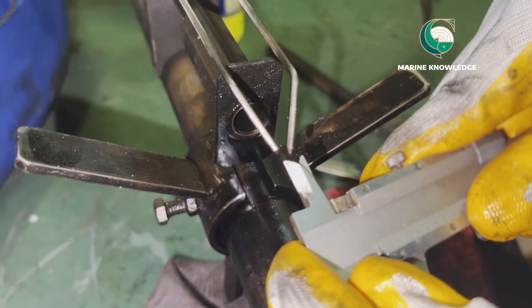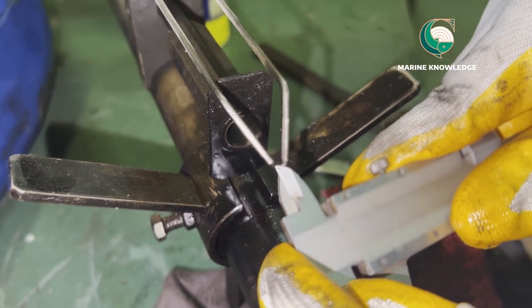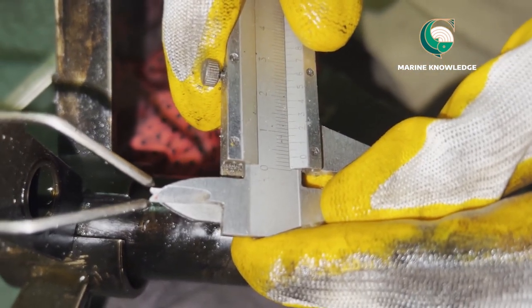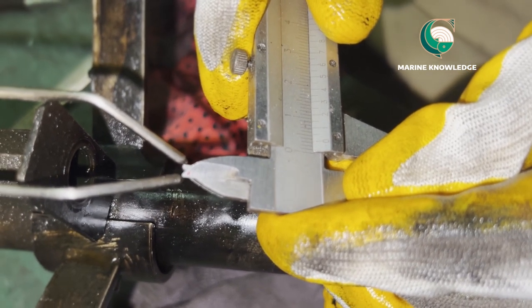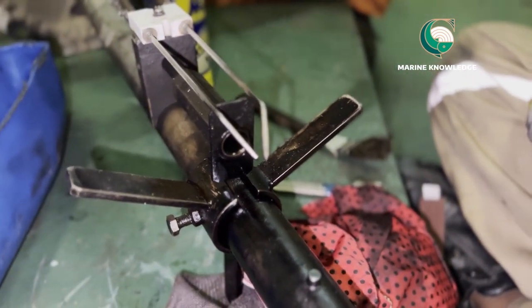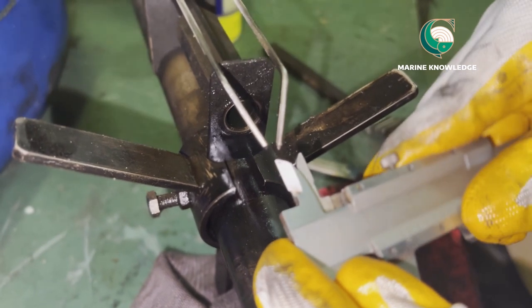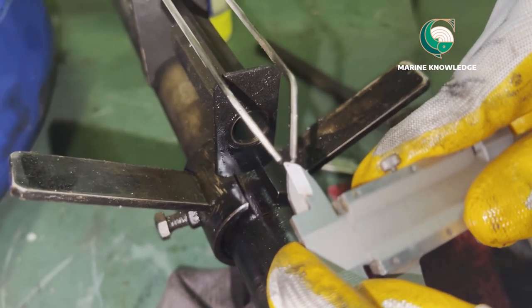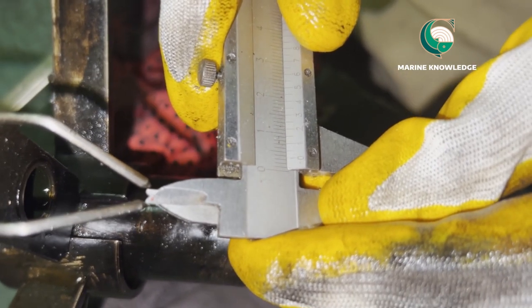This is the first clearance we are going to take: the gap between the ignition electrodes. Take a vernier caliper and measure the gap as we are showing now. If the gap is too large, you won't get a spark between the two ignition electrodes. Use a proper vernier caliper to get a correct reading — place it between the two ignition electrodes and take the gap measurement.